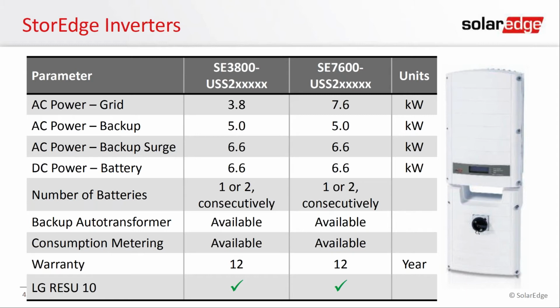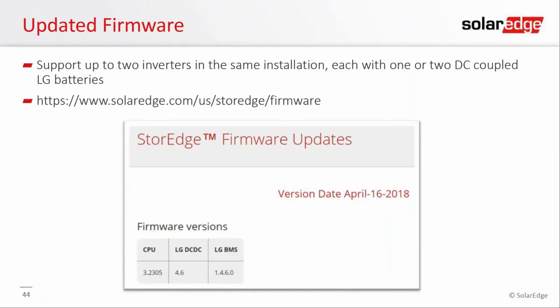You can install 1 or 2 batteries on these inverters that will discharge the battery consecutively. So you won't get more inrush power, but you'll just get a larger fuel tank if you want to think about it that way. It is warranted for 12 years, and like I said, it's compatible with the Resu10H.